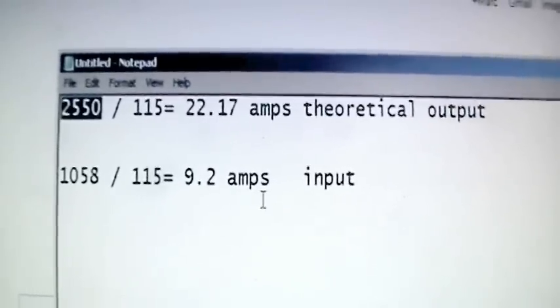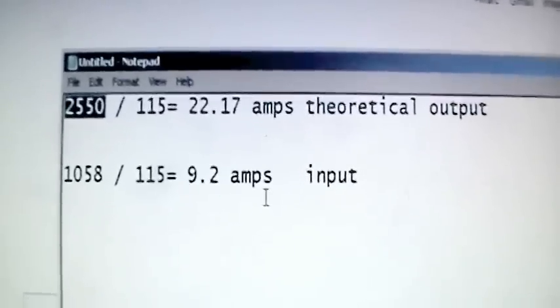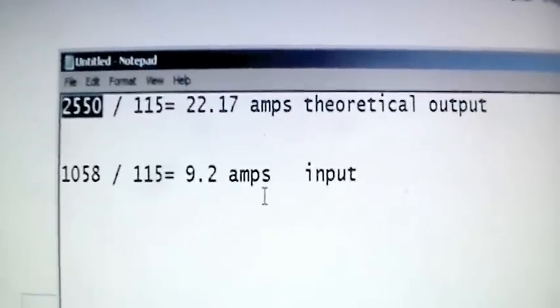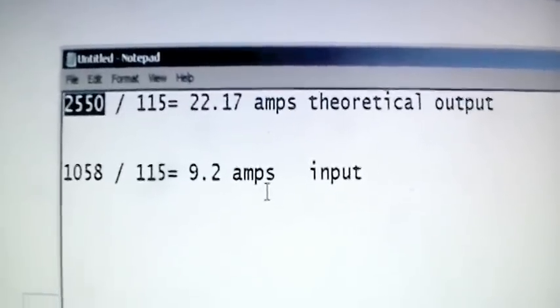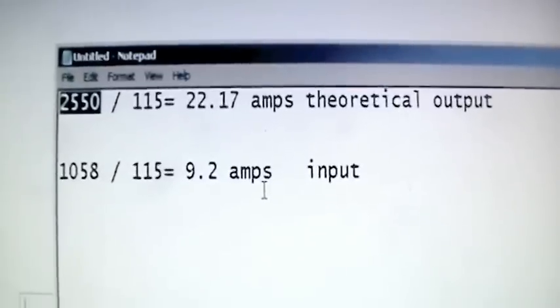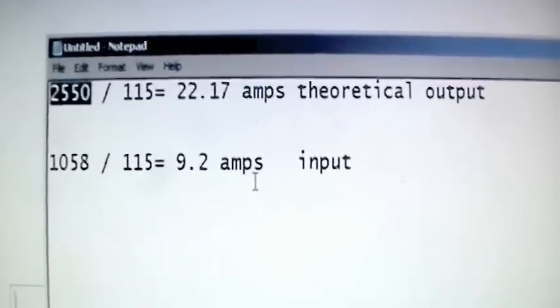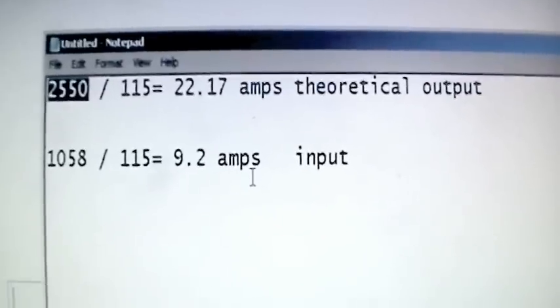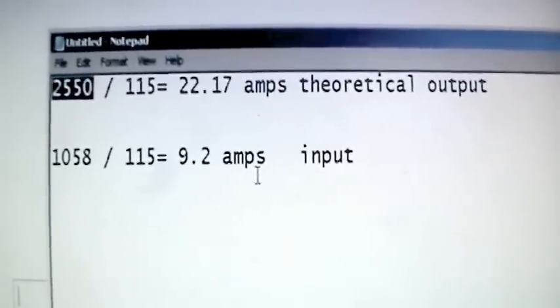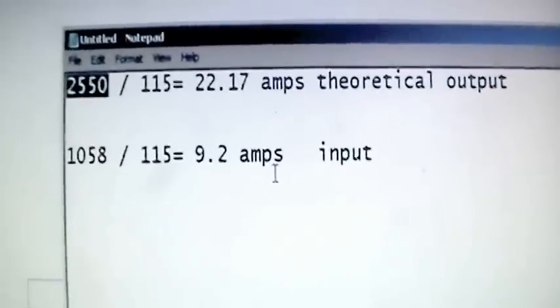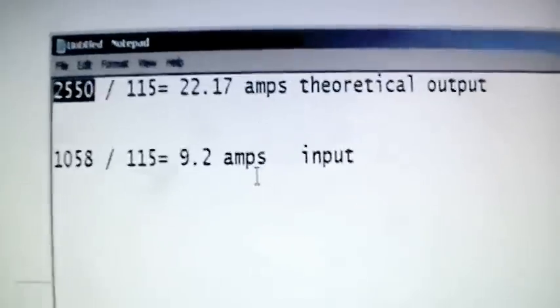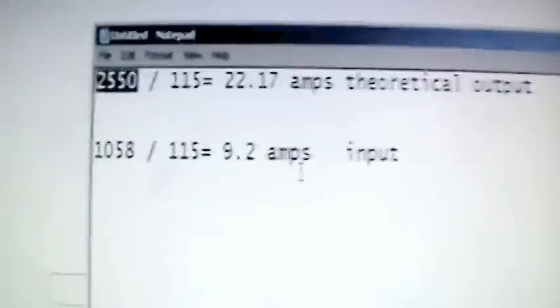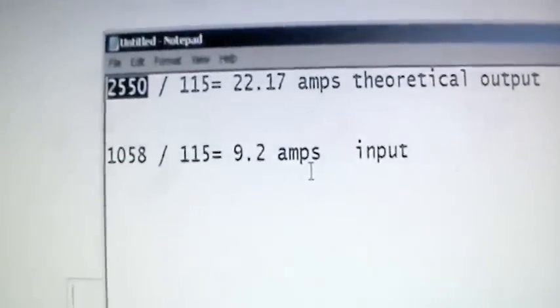22.17 amps is higher than the feed breaker. This breaker pops all the time we put on this circuit. For some reason in this home, the washing machine as well as a circuit in our garage, we have a little electric heater. When the dishwasher, the washer and the heater are on at the same time, it pops the 15 amp circuit. So utilization of this circuit is going to eliminate that from happening, only problem I have is with this little guy.